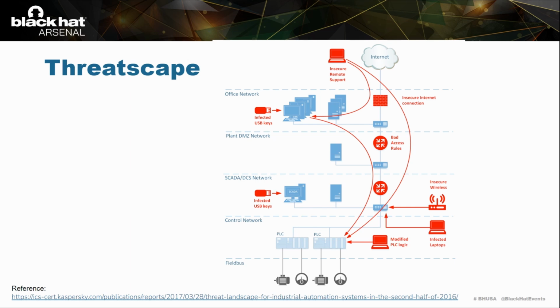As the complexity of these systems increased, there were many different hardware devices and software components produced by multiple different vendors, and these are produced with minimal attention to security. So this definitely increased the risk of known and unknown vulnerabilities, as these were designed to ensure compliance with the CIA requirements. But due to device compatibility, these systems were put at very high security risk, and they were left in highly vulnerable configurations. The safety configuration in a typical SCADA deployment for the field devices is not at all designed to perform well in the event of direct tampering with the control processes.